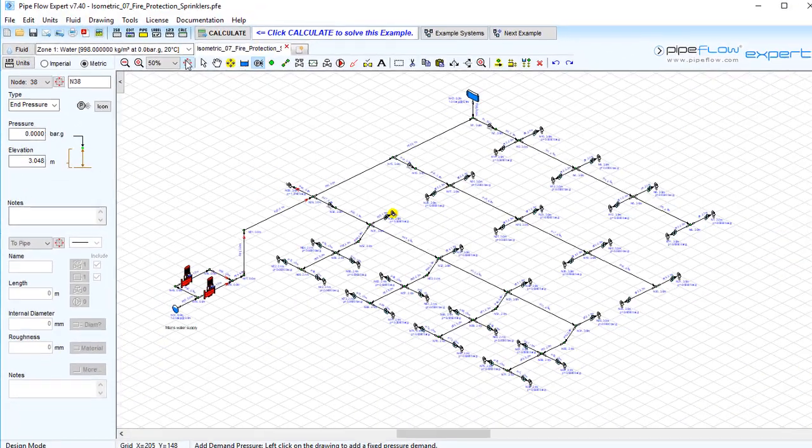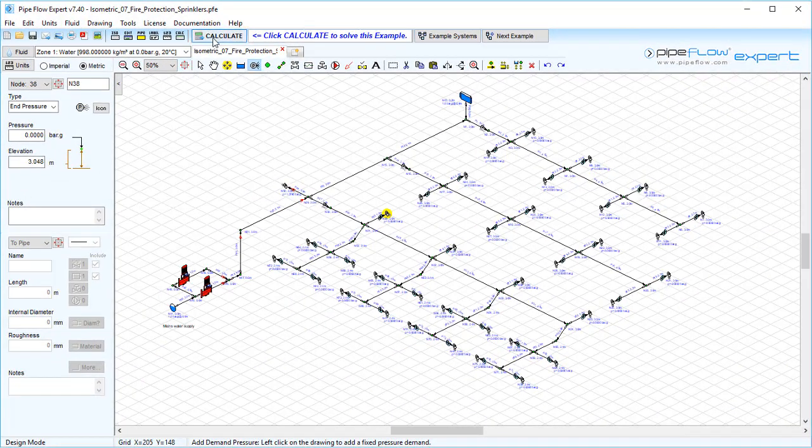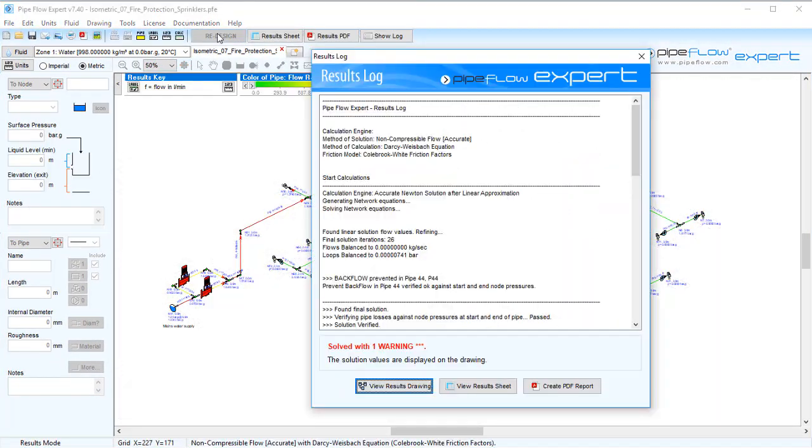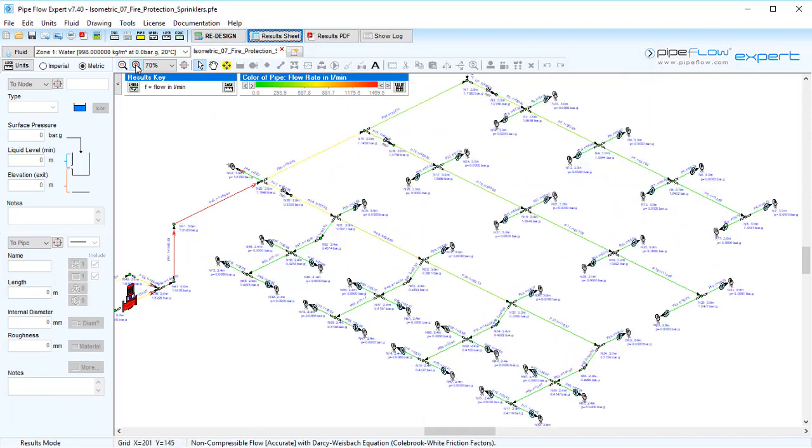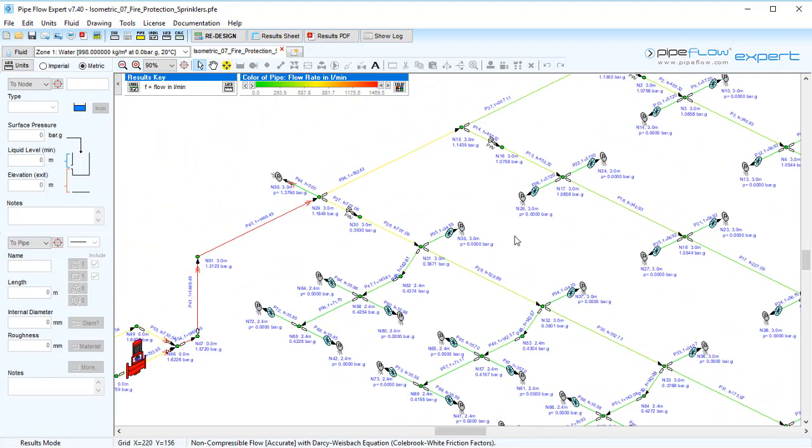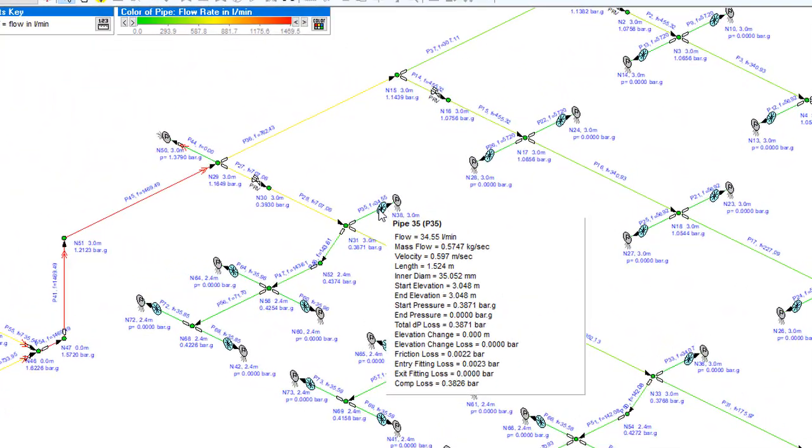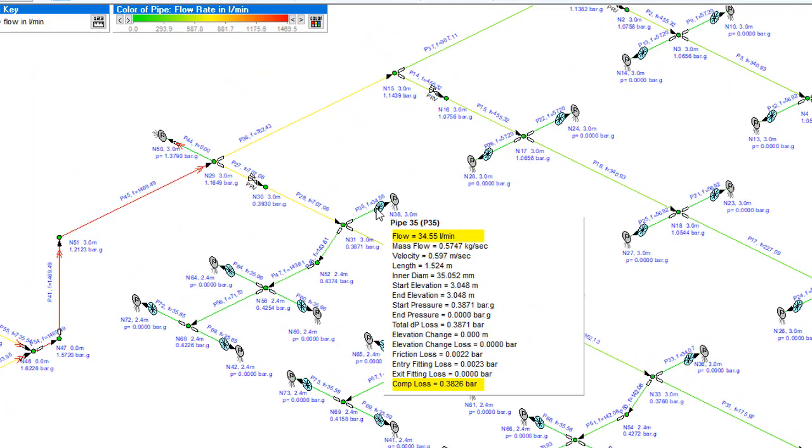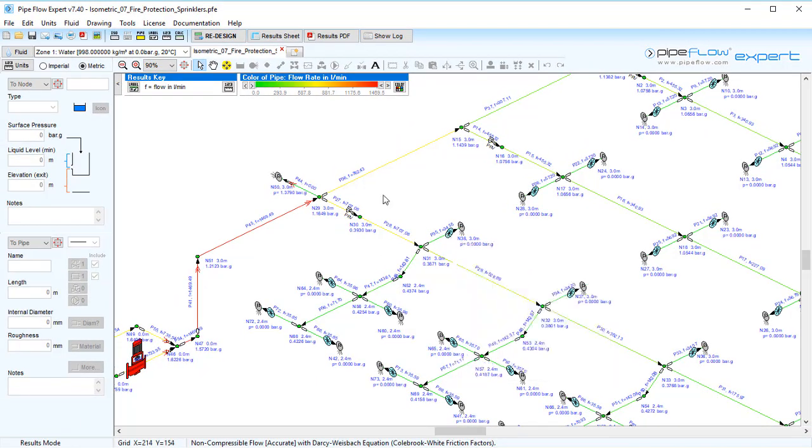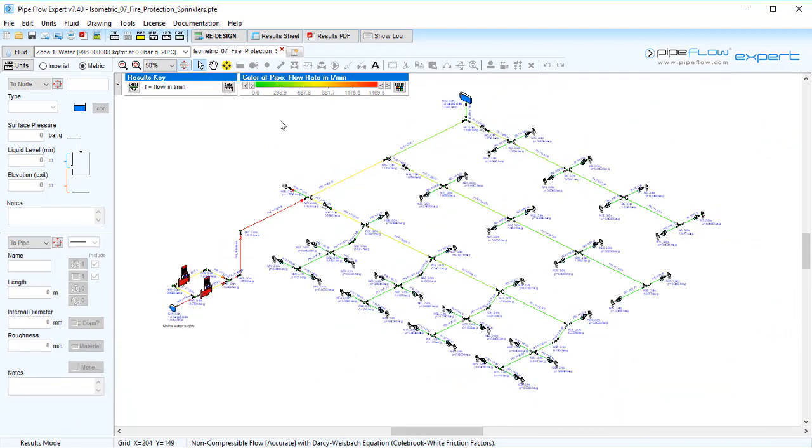After solving the system, we can hover over the pipe in the drawing pane to see the flow rate exiting the pipe is 34.55 liters per minute and the component pressure loss is 0.3826 bar, and therefore the pressure coming into the nozzle is also 0.3826 bar. Thanks for watching this Pipe Flow Expert tutorial video and see you again next time.